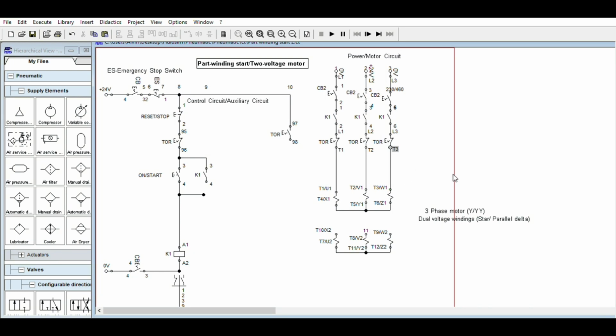So sometimes if the voltage is given this way, there are several ways to connect this one according to the characteristic of the motor. There is a series star. There is also a parallel star. It depends on the configuration of the motor inside. So let's say one star and the next one is parallel star. We will say dual voltage, because you can connect them possibly in high and low voltage. Just refer to the motor's nameplate if that is possible.